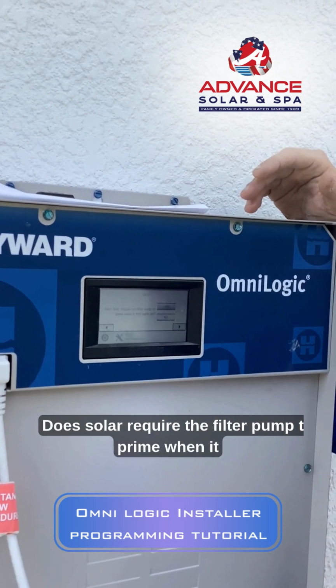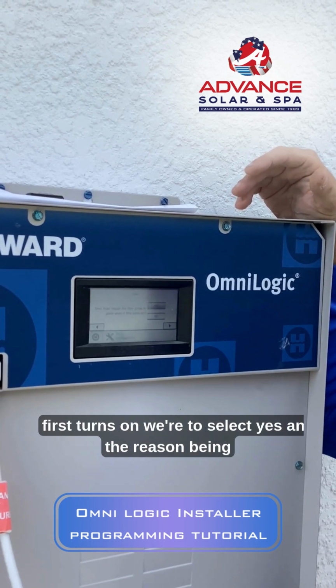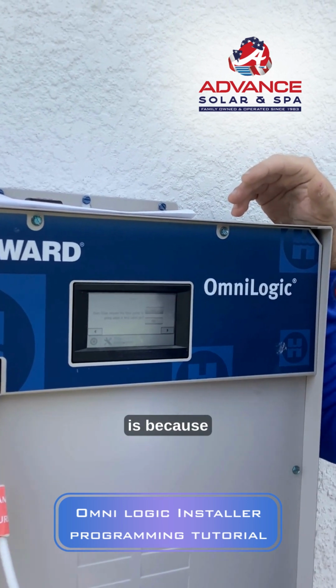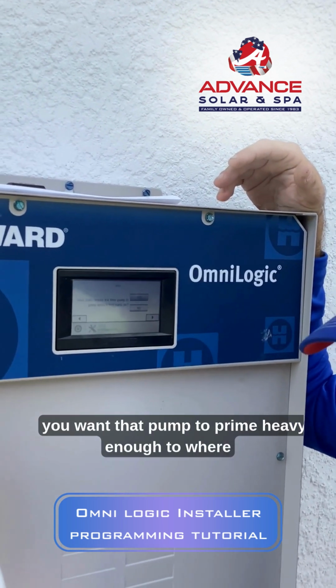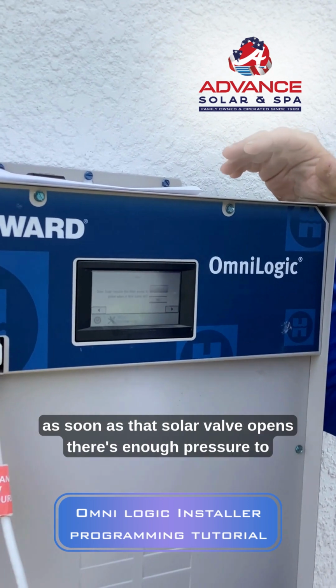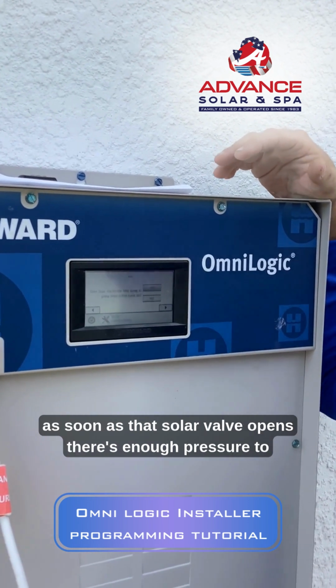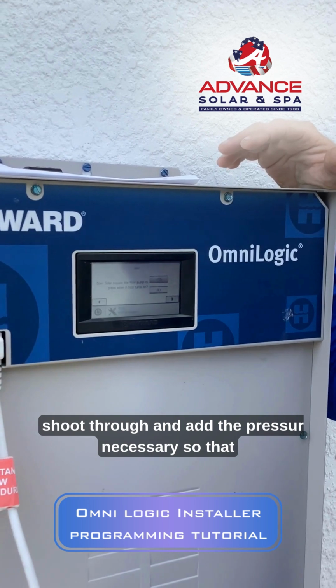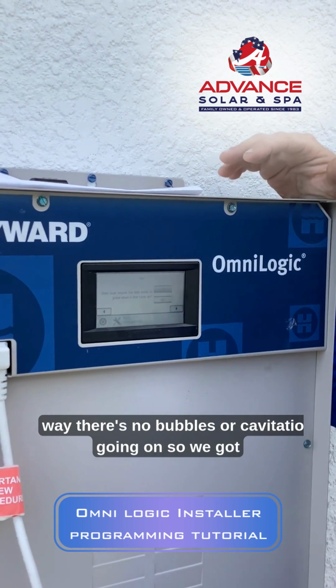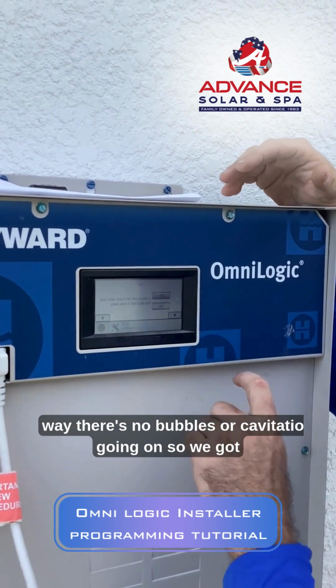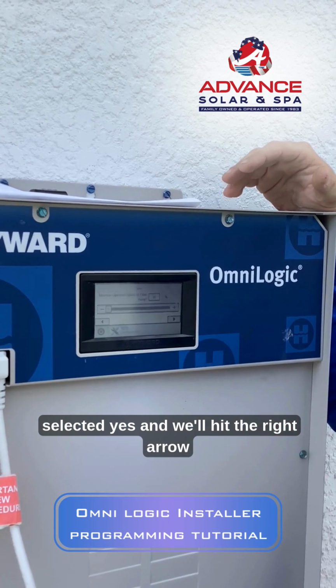Does solar require the filter pump to prime when it first turns on? We're going to select yes, and the reason is that you want that pump to prime heavy enough that as soon as that solar valve opens, there's enough pressure to shoot through and add the pressure necessary, so that there are no bubbles or cavitation going on. So we selected yes, and we'll hit the right arrow.